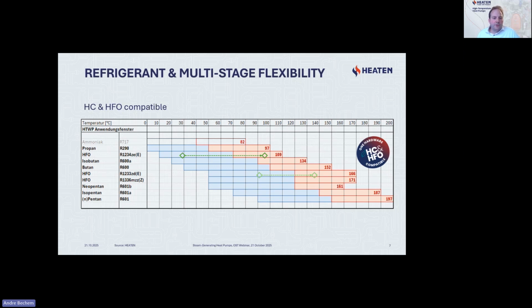What our compressor currently cannot do is water or CO2. Ammonia, it could in theory do with small adjustments, but this is more for subcritical processes at the lower temperature end. So we are really focusing, as mentioned, at 90, 95 degrees plus, and then we use a different set of working fluids.